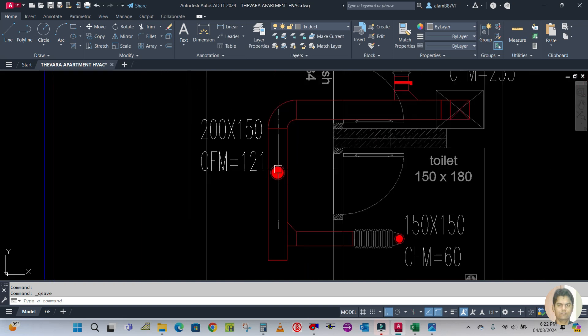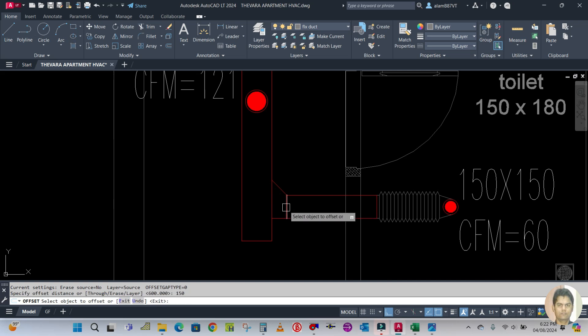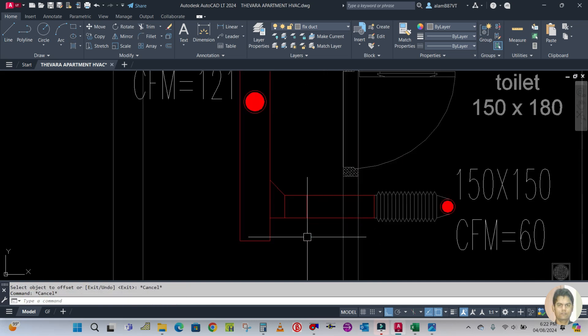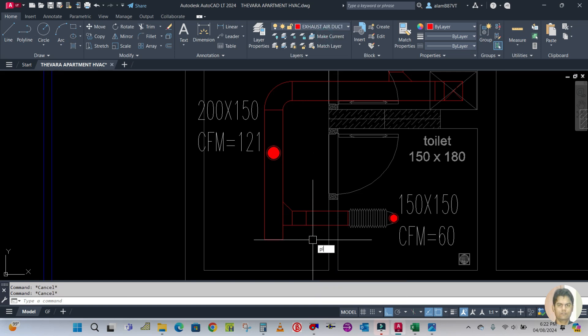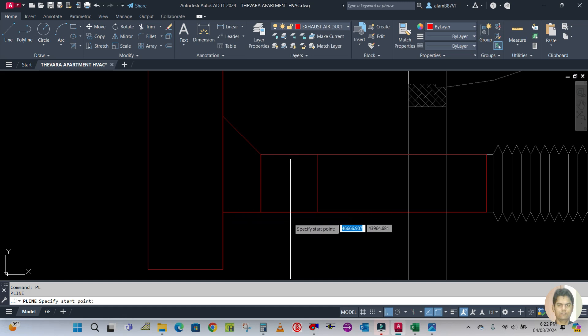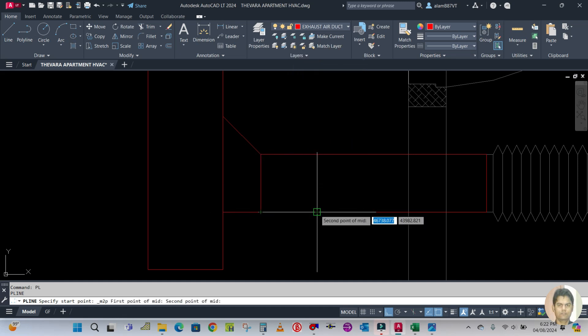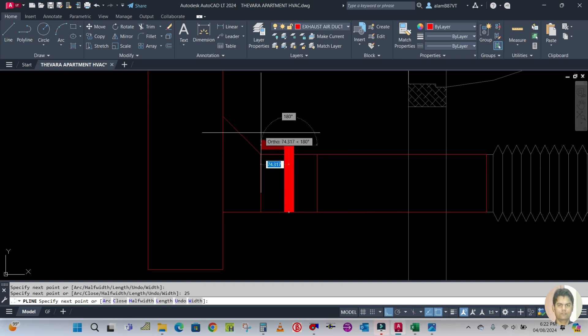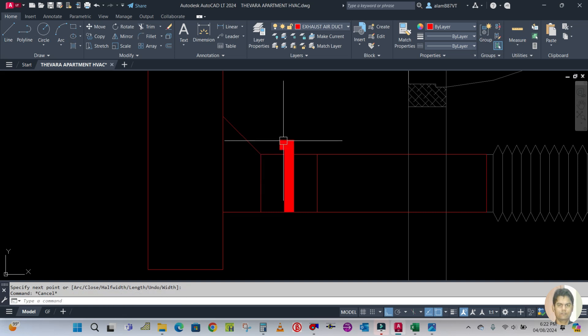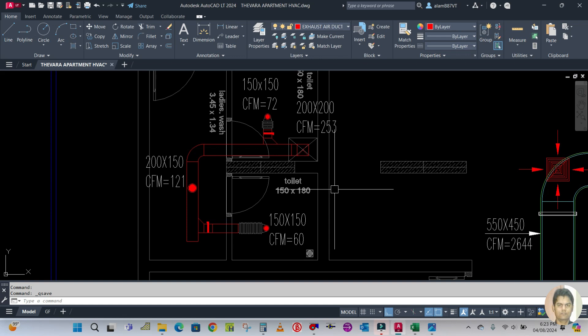The disc valve will be connected directly to this duct. Create one VCD here — VCD length is 6 inch. Use polyline PL to create the VCD between these two lines. Width is 25 on this side and 25 on the other side. This is your VCD.